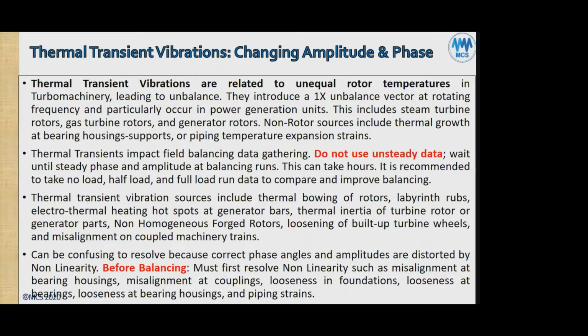This is especially regarding the generator itself. The generator is more sensitive to running at half load and full load, because if it's a 100 megawatt generator, half load is only 50 megawatts and full load is 100 megawatts. That's a lot of difference in thermal heating. That generator runs at 100 megawatt with a lot more electrical load entering through the stator windings and through the rotor. And this greatly increases temperatures.